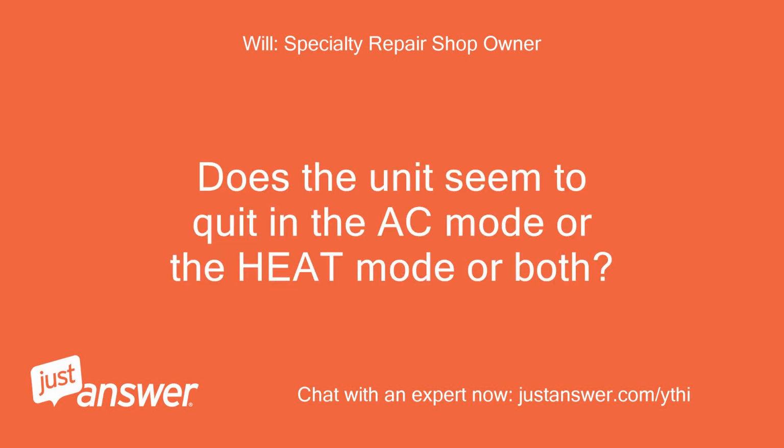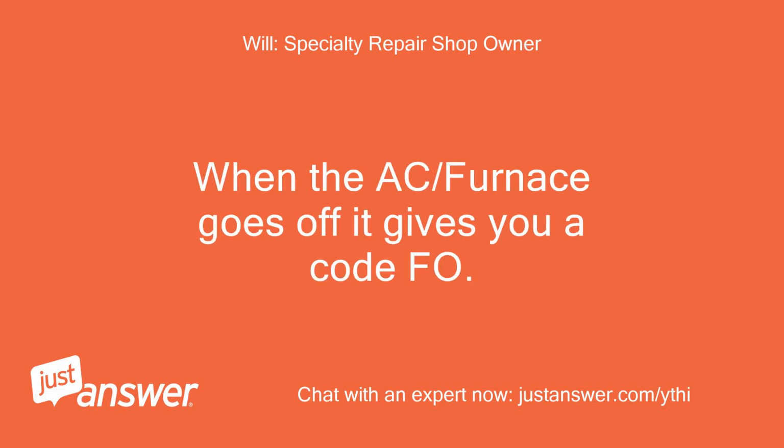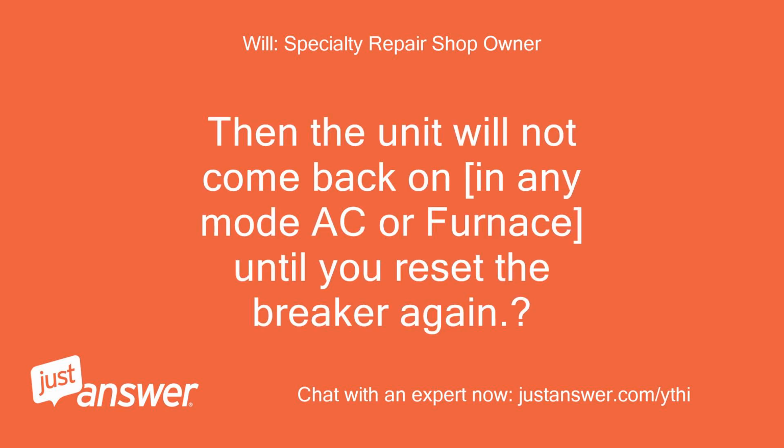Does the unit seem to quit in the AC mode or the heat mode or both? When the AC/furnace goes off, it gives you a code F0. Then the unit will not come back on, in any mode, AC or furnace, until you reset the breaker again.